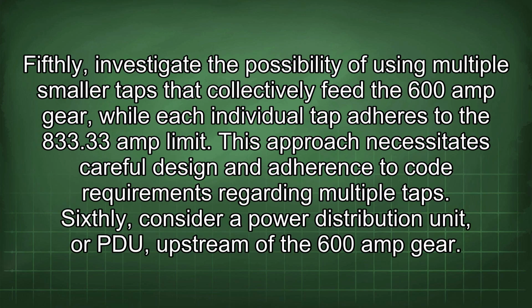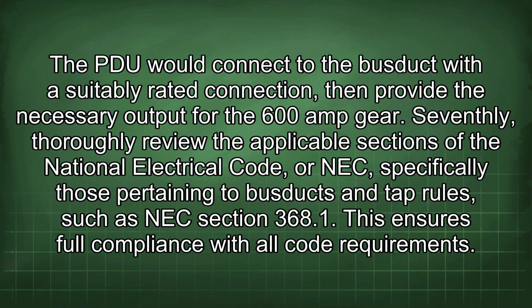Fifthly, investigate the possibility of using multiple smaller taps that collectively feed the 600 amp gear, while each individual tap adheres to the 833.33 amp limit. This approach necessitates careful design and adherence to code requirements regarding multiple taps. Sixthly, consider a power distribution unit, or PDU, upstream of the 600 amp gear.